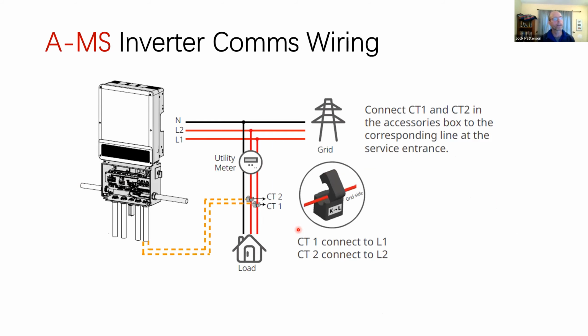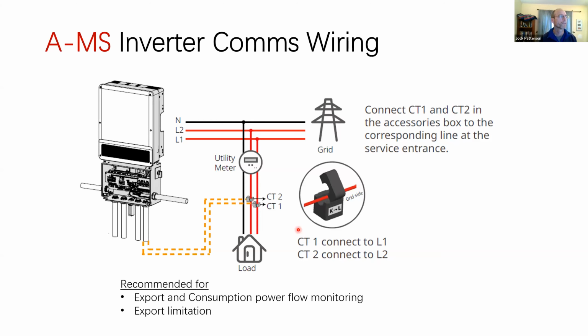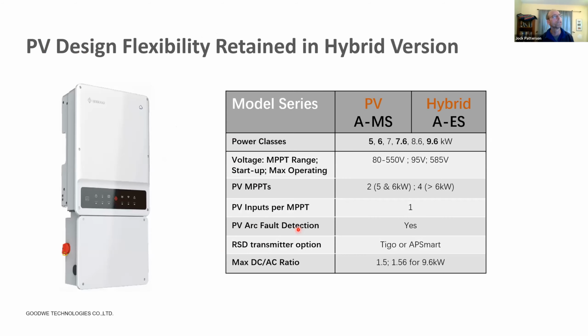That was power wiring. Now we've got comms wiring, which is really just the CTs. Remember, the Wi-Fi module just plugs in. The only thing you're doing on a PV inverter for external comms wiring are the CTs, which will wrap around your L1 and L2. And then you'll do in the commissioning process a meter test to make sure all that's done correctly. The real benefit of CTs is, again, on the SEMS monitoring platform to see how much of the energy is going out to the grid, how much is being consumed. But you'll also want to do this if you're in a utility or an area where you can't export, or you have to limit your export. You need some method of doing that. So the CTs give you that control.